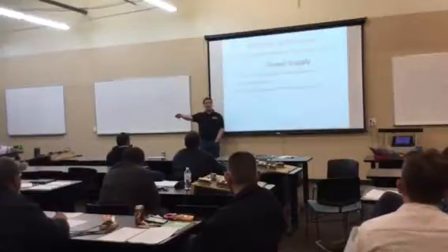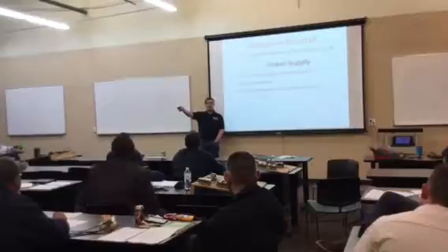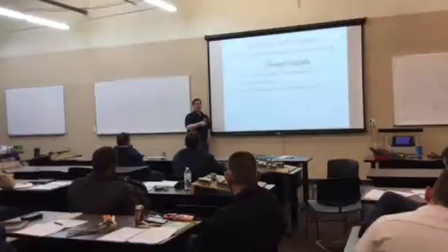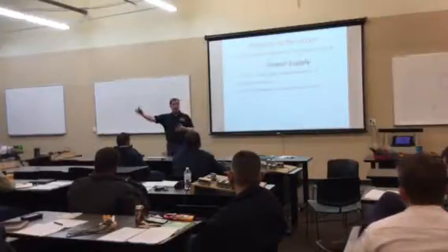So in order to compensate for that, when we're going to do a panel upgrade in a house, we're going to remove that whole panel and put one in that's physically larger so we can handle more amps. The wires that feed it are going to be physically larger so they can handle more amps. We're not changing the voltage, we're upsizing the diameter of the wire so they can handle more current so they can supply more. It's always going to be limited by something, and that's the physical size of the wires, and that's protected by the circuit breakers or overcurrent protection devices.